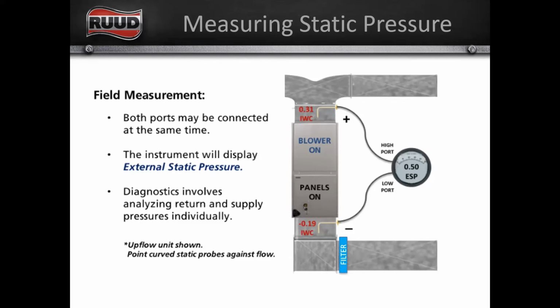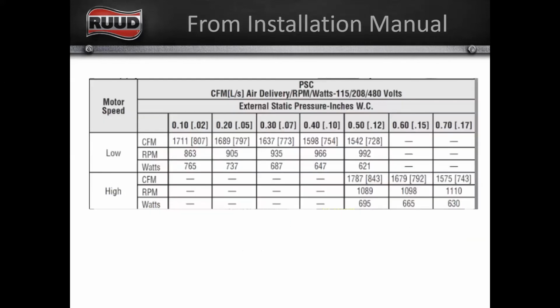Awesome. Does that mean that we're moving the right amount of air? No, it doesn't, not yet. And the reason for that is we don't know what blower tap we're using. So the other part of this equation is, when you're checking static, you have to know what blower speed or what blower tap you are using, or you don't really know how much air you're moving, right? So here's a blower table for a PSC motor, and we just measured 0.5, or a half inch, of static. Well, if we're on low speed, we're moving 1,542 CFM, or 728 liters per second, if you want to use the metric system.